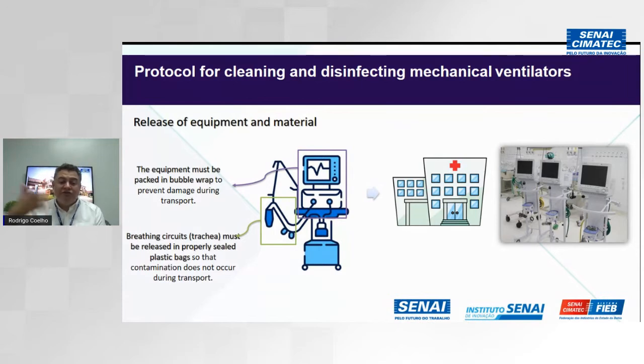It must be highlighted that you also need to send the paper where all the activities that have been done on this equipment are described: all pieces that have been changed, all interventions on the pieces that you did. So any kind of details regarding the electronic maintenance, the mechanical maintenance, and also the way that you cleaned this system. This is very, very important, where people can see how you clean, and what you use to clean. Because then the hospital is able to ask and to agree if what you have done is enough or not.